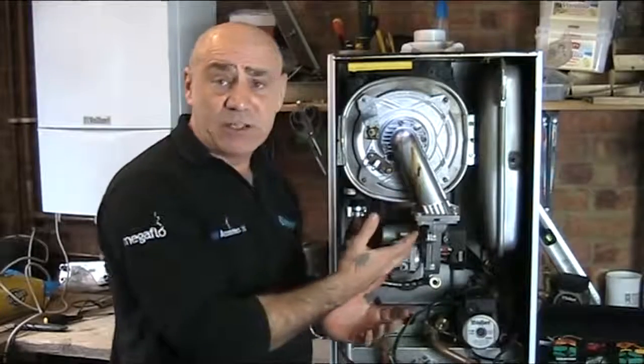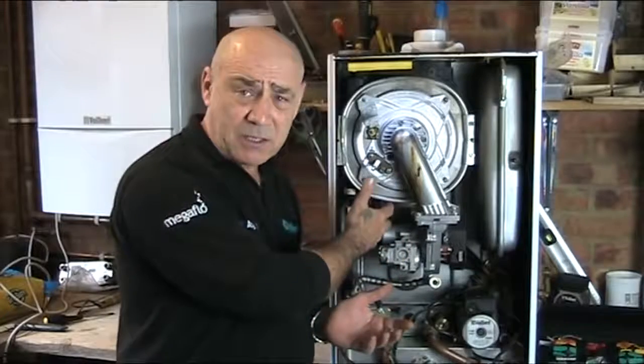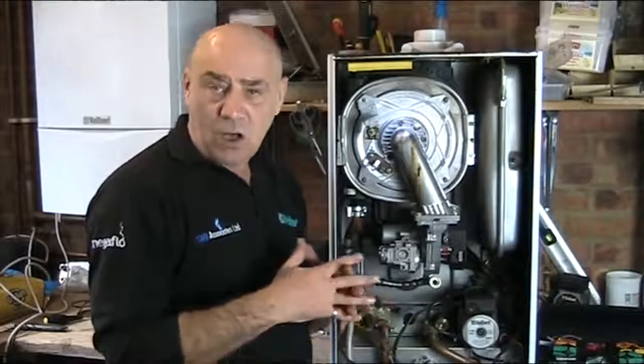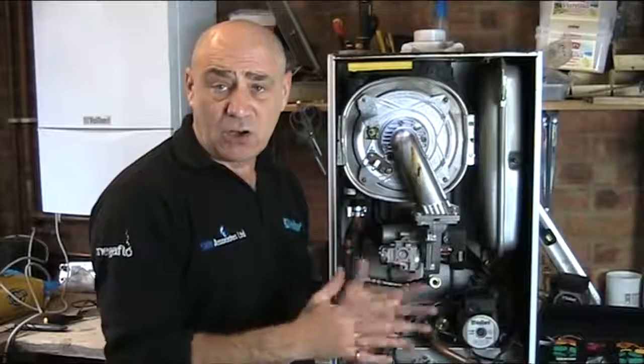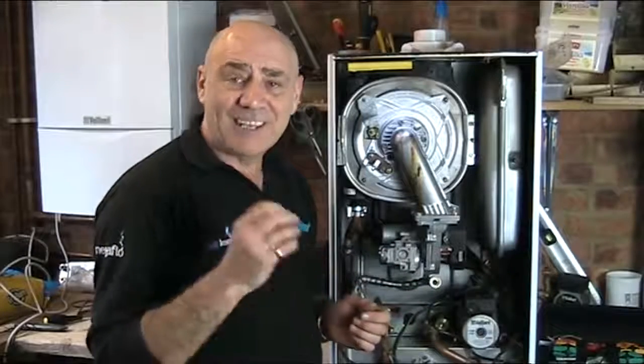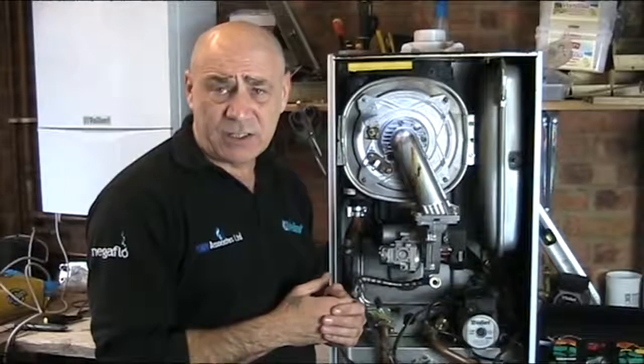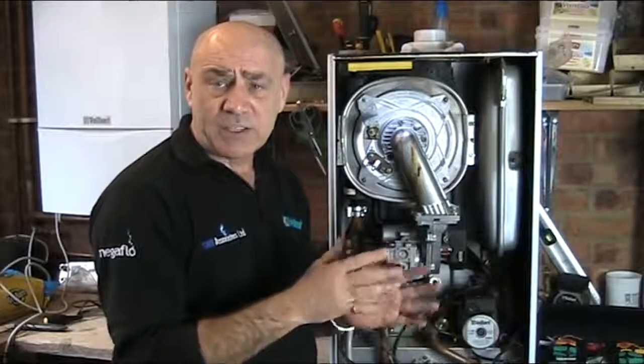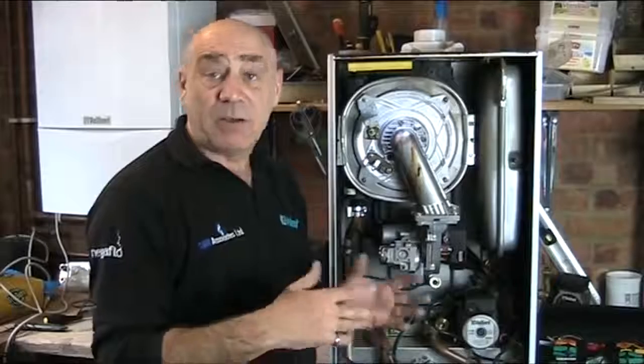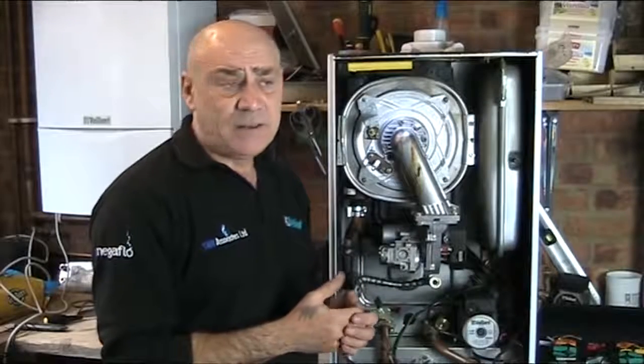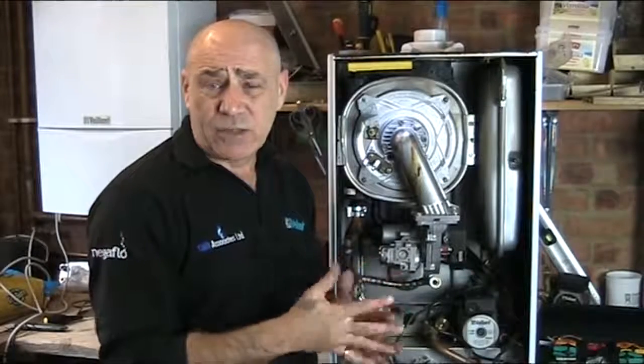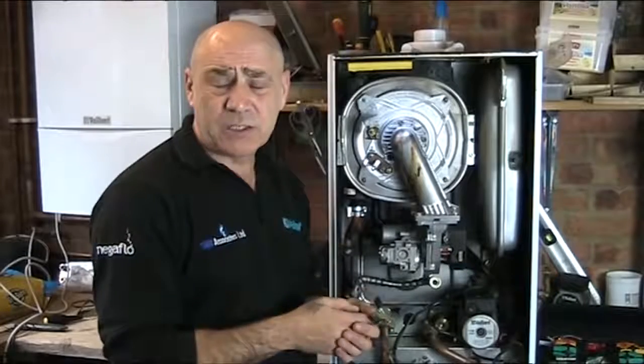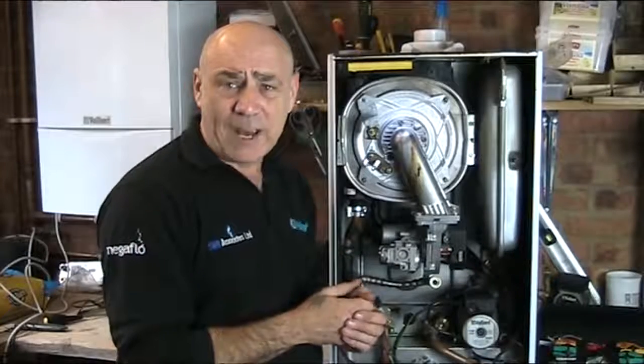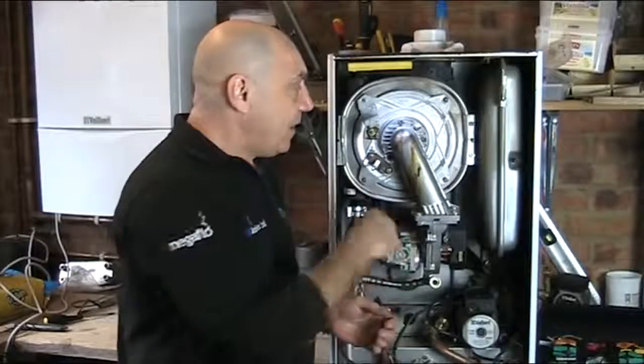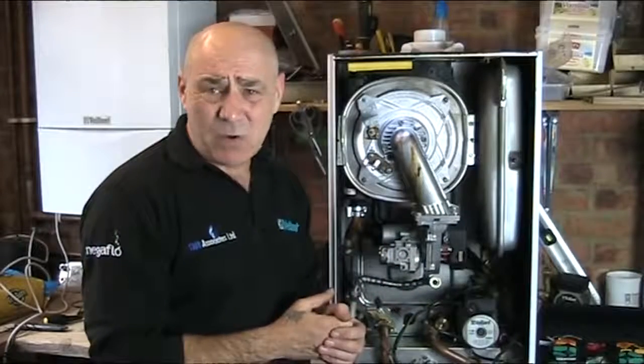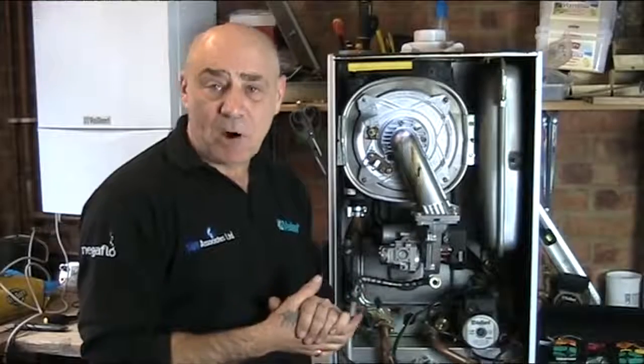Now the new graphite seals that go into these systems, or these combustion chambers, longevity wise they last a lot longer and are a lot more robust. That doesn't mean to say though that it doesn't need changing. We're just starting to find now with some boilers, not the ones that we've serviced, but boilers that are coming through the system now that haven't been touched or serviced for 4 or 5 years, that the graphite seals are starting to break down quite badly. So realistically that burner needs to come out at least every 4 years, but we do it biannually.